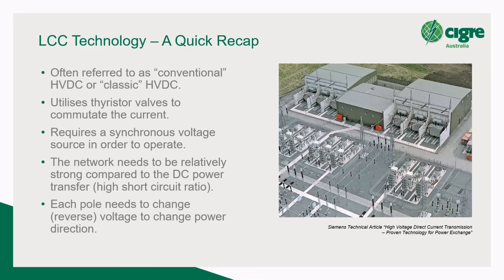So one was supposed to switch out, and the other was supposed to switch in, but because of the disturbance in the AC voltage waveform, they both stay on and they create a short circuit on the DC side. Okay, interesting thing about LCC is over the years, like I said, it's been out since the 1950s.